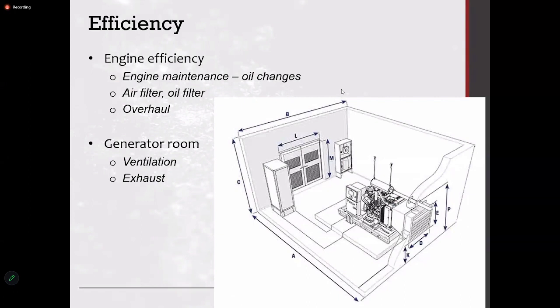For generator energy efficiency, the basics are just like an engine: oil changes, filter changes, and overhaul. The other key thing is the generator room, how you have installed the room, because the key point of overload is not the power, more than the power, it is the temperature levels. You have to see whether it can cool down the rising temperature due to the load, in a ventilated space. I'm talking about air cooled generators, where the radiator part, the front part, is exposed to outside and you take out the hot air. You have to have a proper suction. If the suction is blocked or not giving enough air, it is a problem. Suction has to be generally bigger than the exhaust, because suction is not forced.